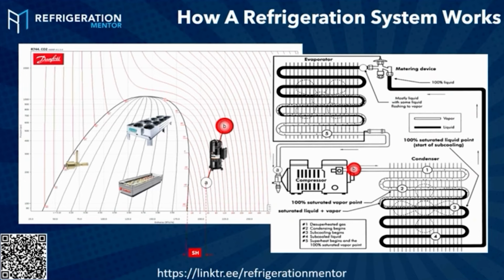So everything past that compressor discharge service valve, actually right from the valve in the scroll or the semi-hermetic or the screw compressor, right when that last squish of gas happens, or compression of gas, that's the hottest point in the system. Everything from there is desuperheating, all that going up to your condenser. Desuperheating. Then we get to the condenser, we start to condense. So you'll see it go through here, and then we hit this one point.